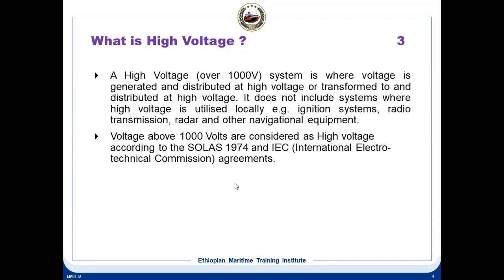So what is a high voltage? Any voltage of 1000 volts and above is considered to be high voltage. A high voltage system is a system where voltage is generated and distributed at high voltage, or transformed to and distributed at high voltage. So it does not include systems where the high voltage is only utilized. You see, high voltage is produced on board ship in many other things also. If you see an ignition transformer, it is sometimes 13,000 volts. In the radar also, they use very high voltage, but those ships are not considered to be high voltage ships. Where a voltage is generated and distributed, those systems are known as high voltage.